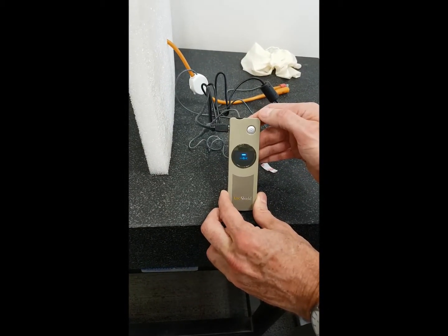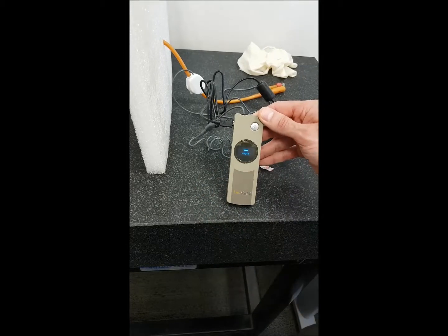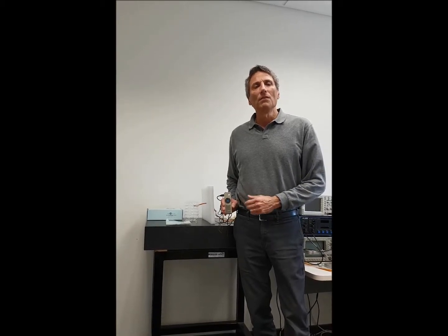The UroShield driver works intermittently in cycles of 15 minutes active followed by 5 minutes idle. You can hear a low hum sound from the actuator during the active period. Important note, the UroShield should be active continuously, 24/7, except for the time when the patient needs cleaning.